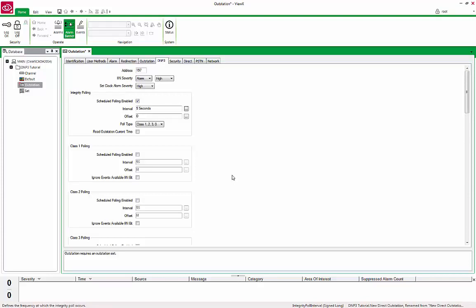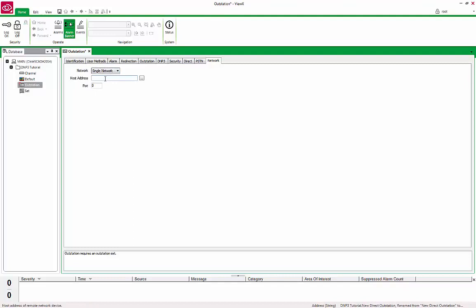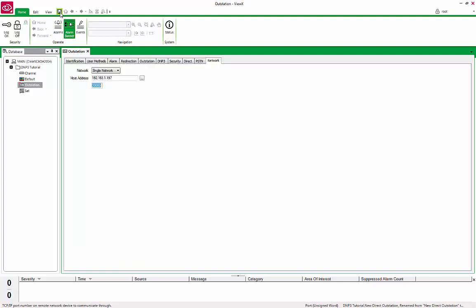Finally, go to the Network tab. Select Single Network from the Network drop-down. Enter the IP address of the device. In this case, 192.168.1.197. The Port field here is the port on which the RTU is listening for inbound communications. In our setup, it is 20,000 for UDP communication. Save the form and close it.